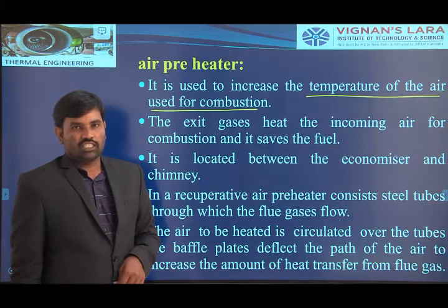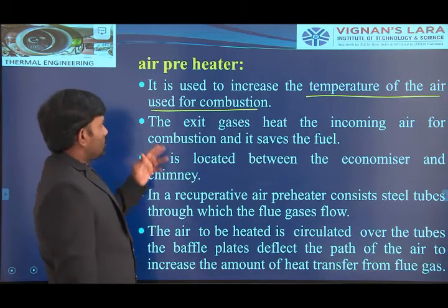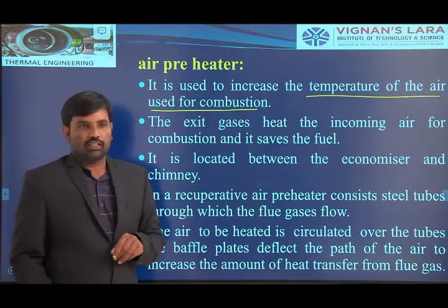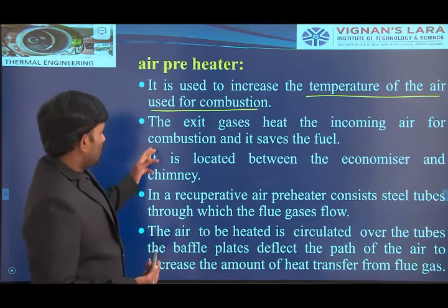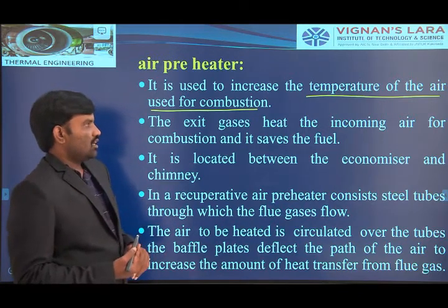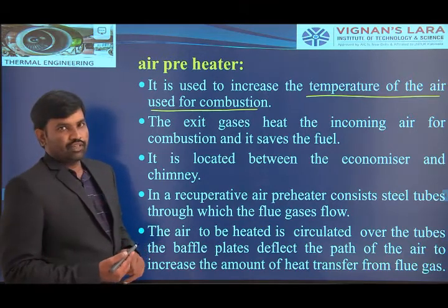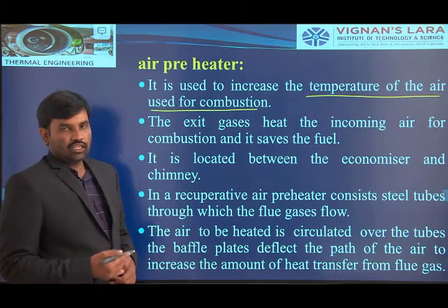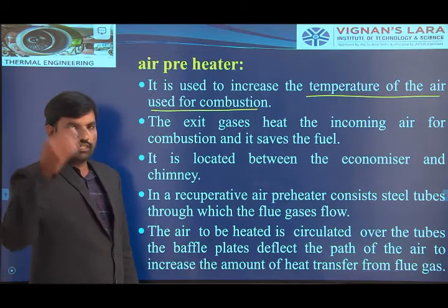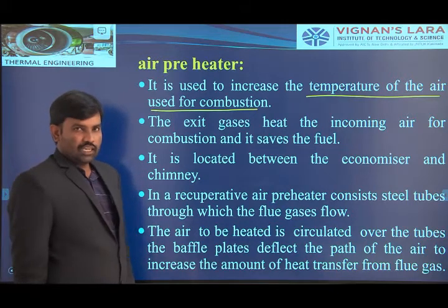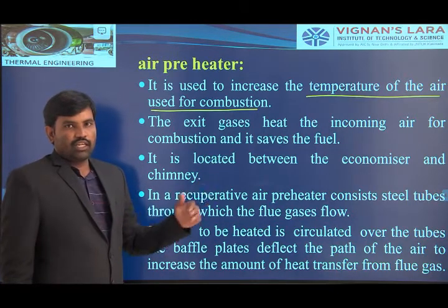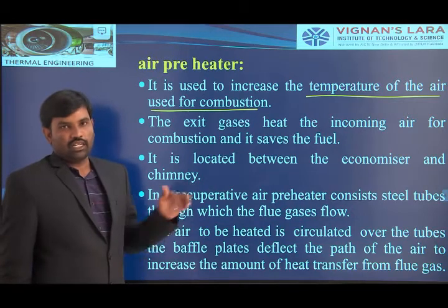In order to increase the temperature of the air, we use the air preheater to increase the combustion efficiency. The exit gases heat the incoming air for combustion and it saves fuel. During the flow of gases from the combustion chamber to the chimney side, those gases heat the incoming air in the air preheater tubes.